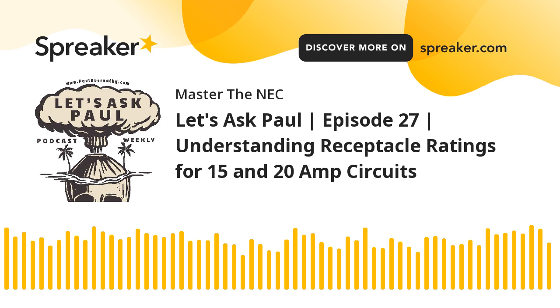Pretty straightforward, right? Again, summary: 15 amp breaker, 15 amp duplex, perfectly fine. 15 amp breaker, 20 amp receptacle, duplex, not good. That's a violation. Okay, violation. A 20 amp circuit breaker with a 15 amp duplex receptacle is perfectly okay. And that is per 210.21(B)(3) and associated table. Also, 20 amp circuit breaker, obviously a 20 amp rated duplex is perfectly fine as well. Okay, so that's okay. So we've pretty much covered those with the duplexes and the 15 and 20 amp branch circuits.